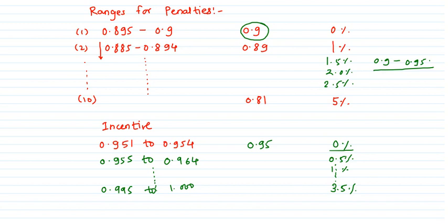Okay. These are some of the incentives and penalties which are applicable now in our billing. As I have discussed, earlier there was a penalty only for lagging power factor, so RKVAH lagging. But now there is a power factor related penalty for leading power factor also.